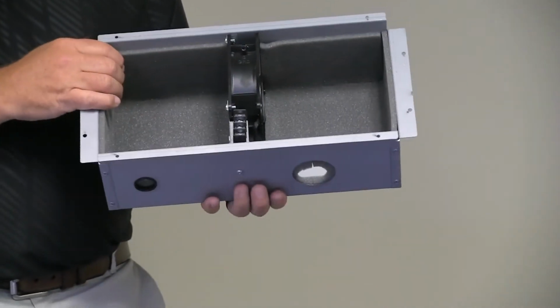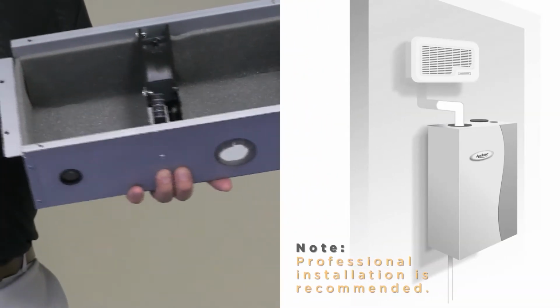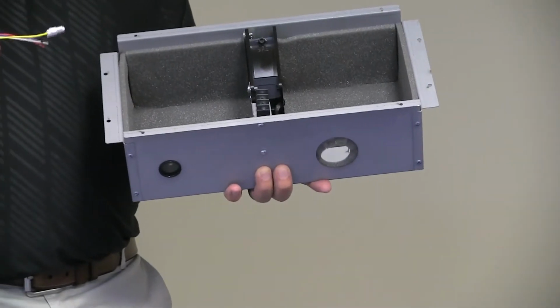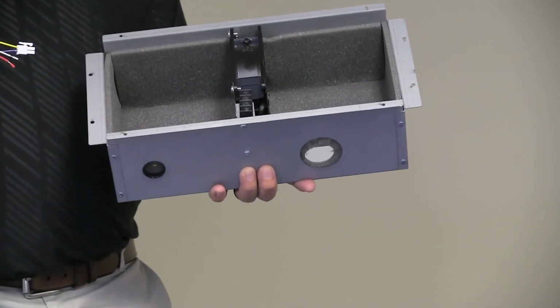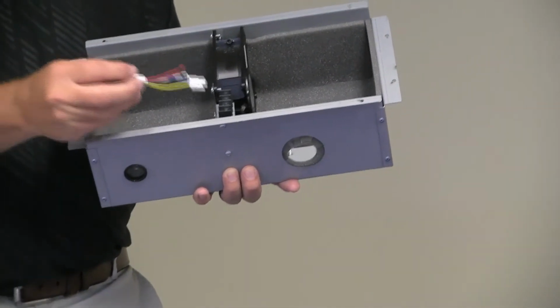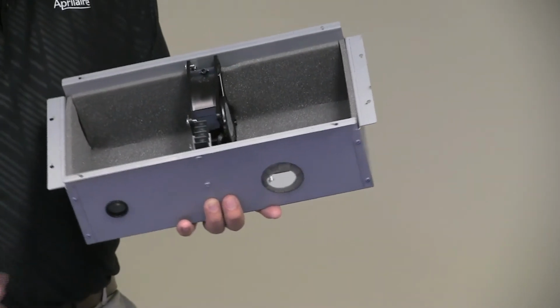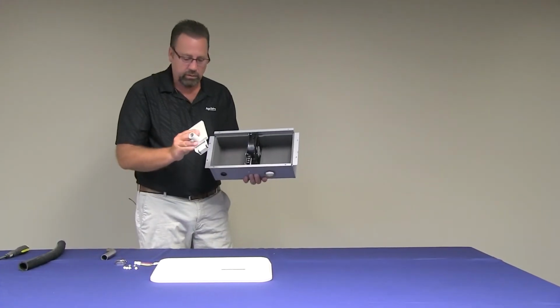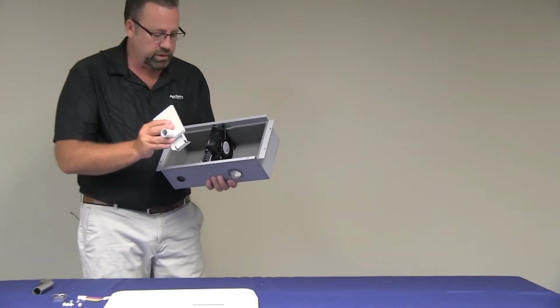The fan actually gets powered from the steam humidifier itself. We give you a little adapter to go in there to tap into the transformer power inside of the steam humidifier to get the 24 volts needed to power the fan pack. Makes it very simple. The steam block is separate here, as you can see.